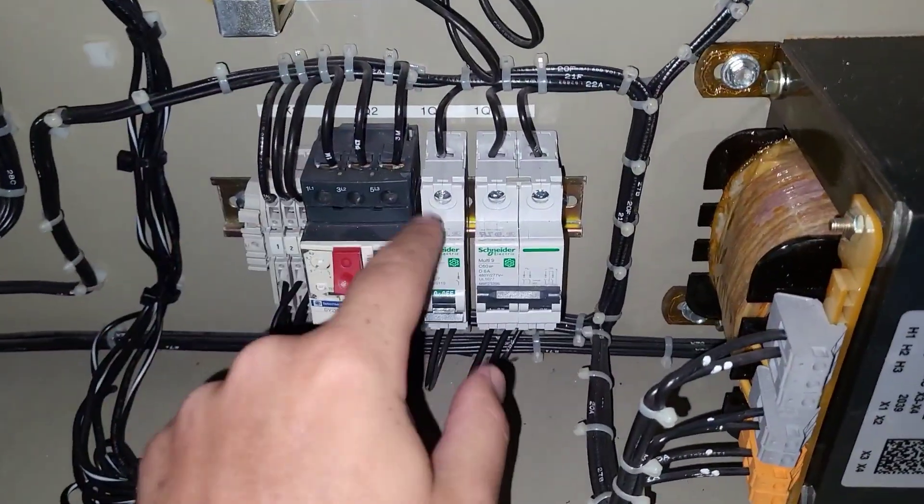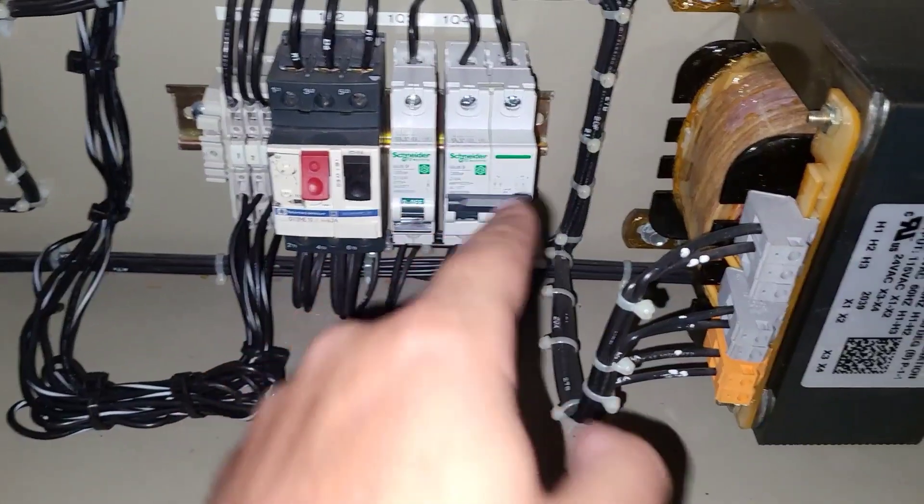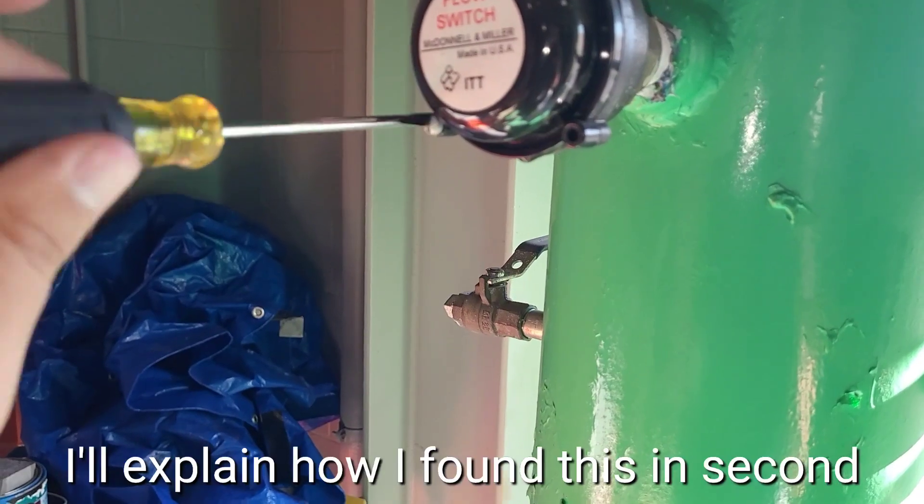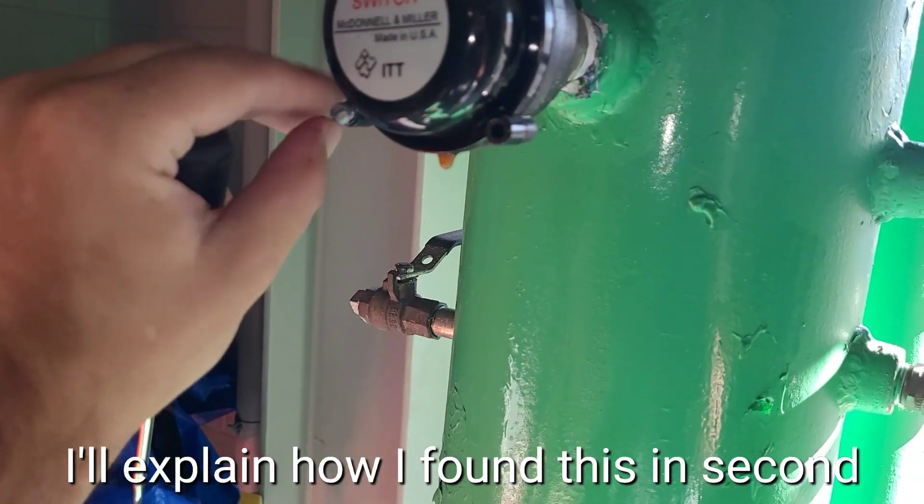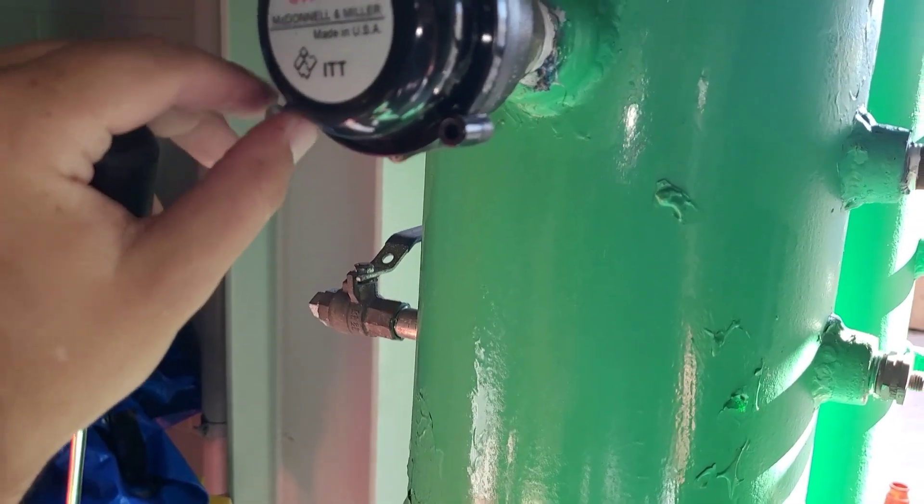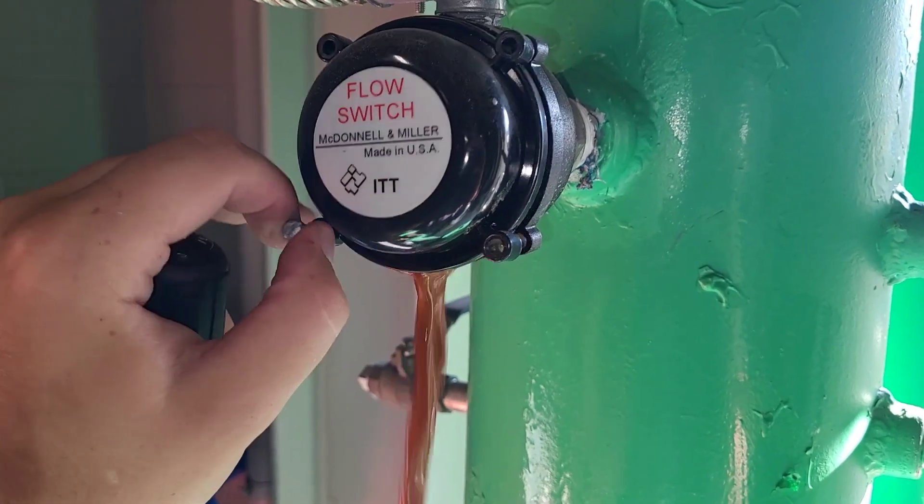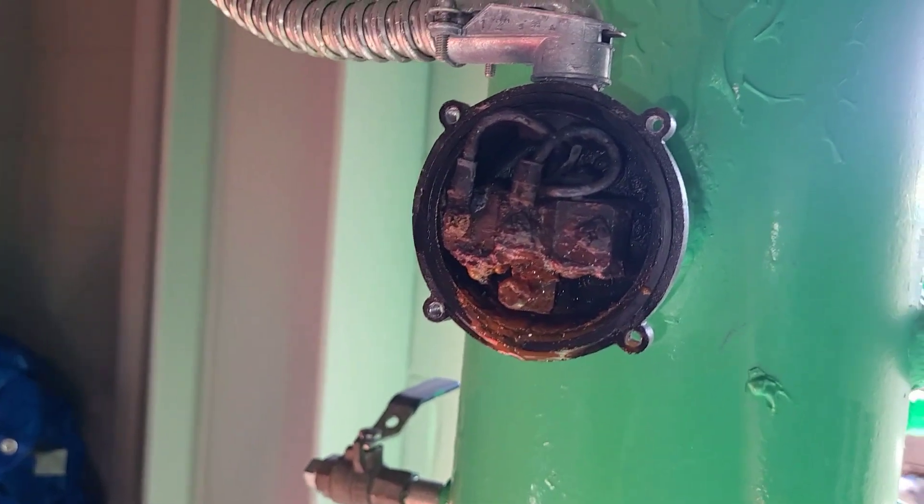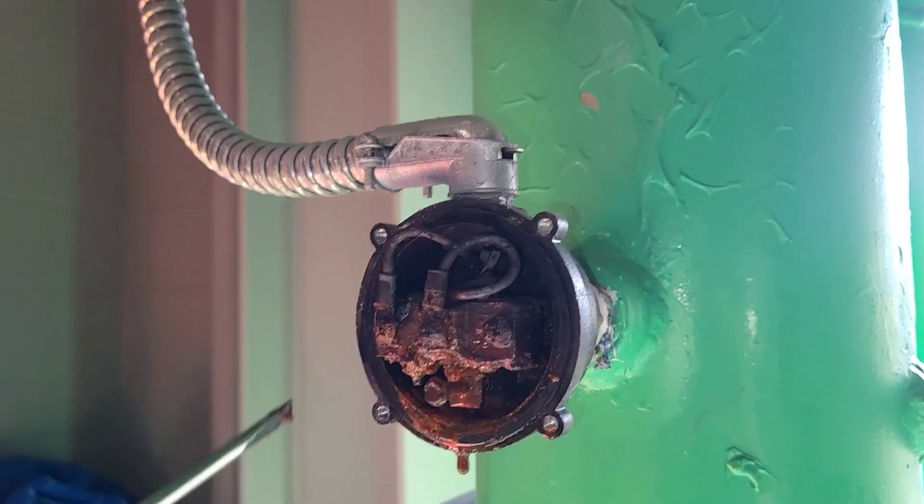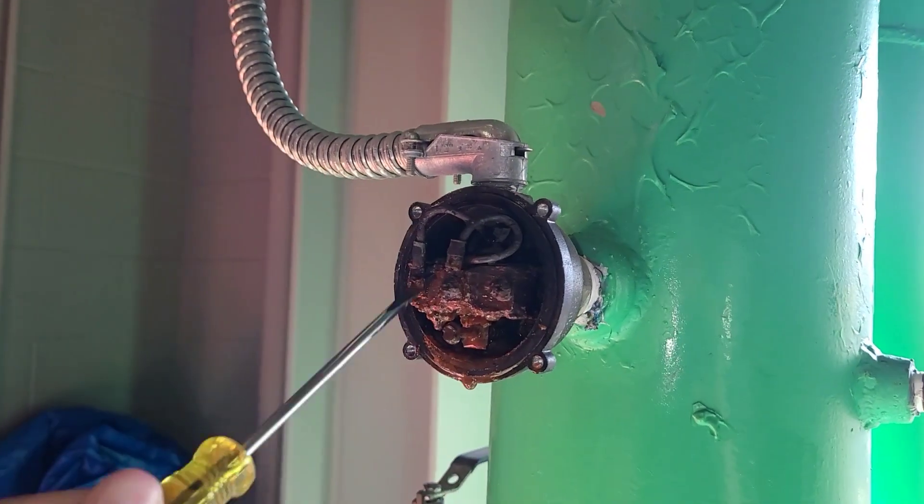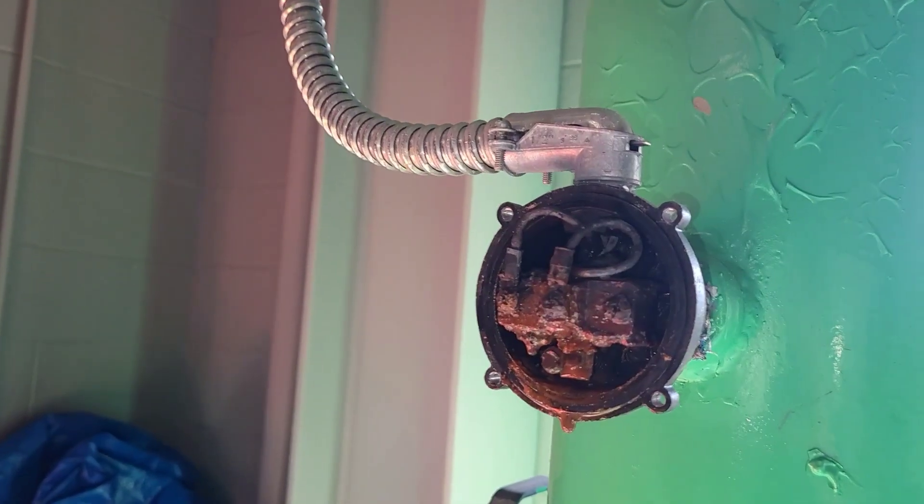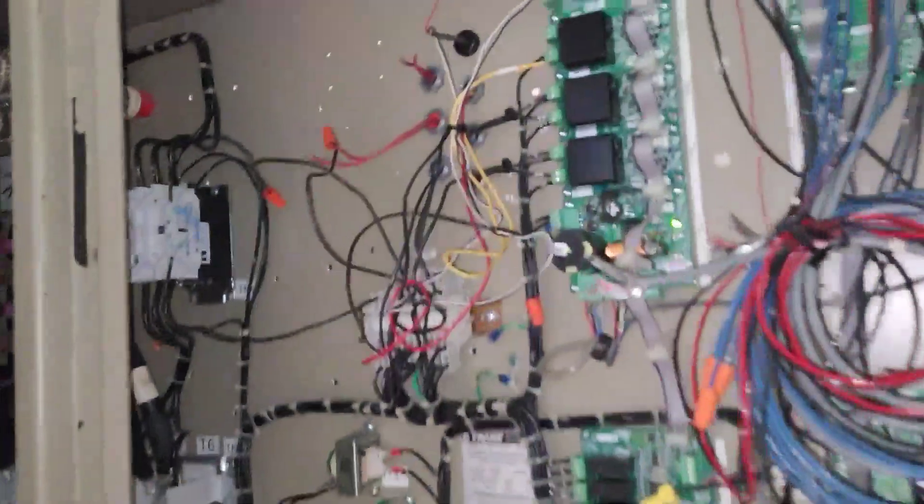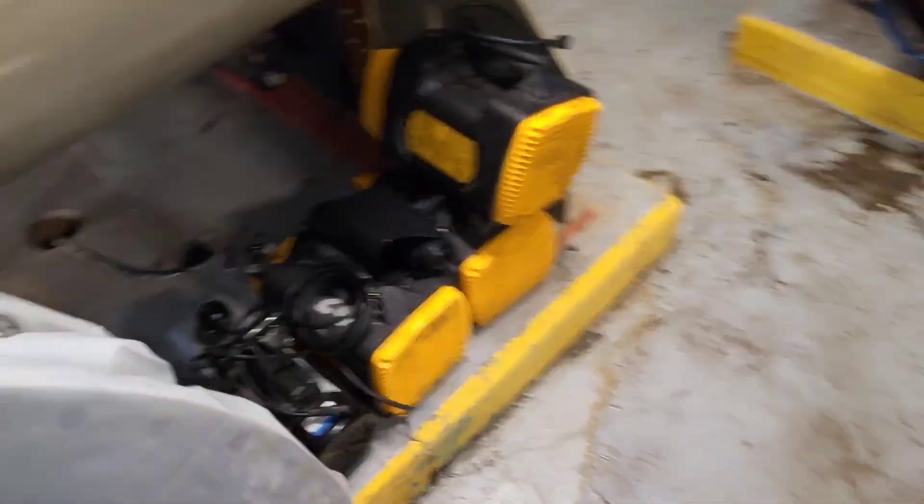I think this is the output side of the controls transformer. Here is our problem. We're getting a short. I haven't got this cap off yet as bad as you can tell. It's significantly dripping. Oh boy, yep, that is our short right there. It's just steadily leaking at the stem. I'm hoping we get the water off of it. We can at least kill the short—direct short to ground. Let me get a rag, wipe that off.